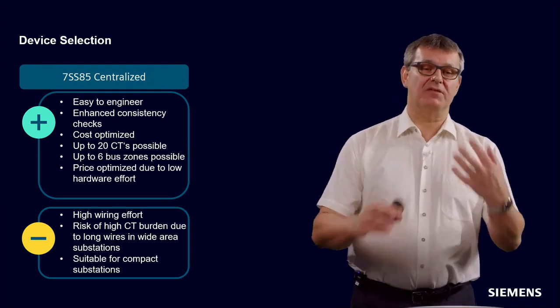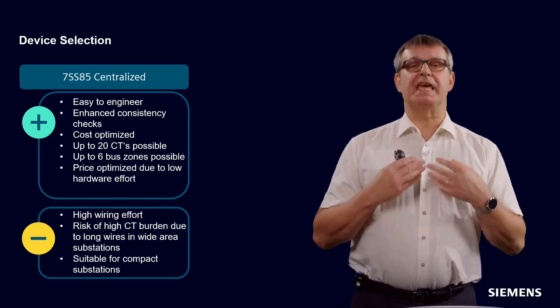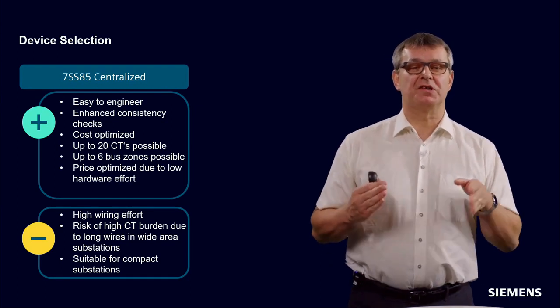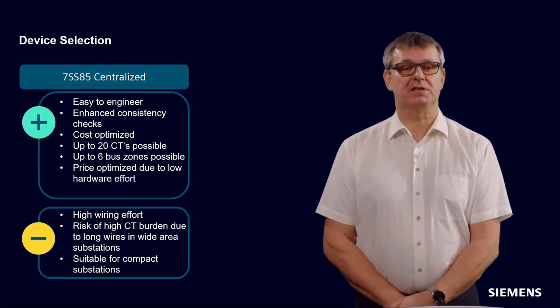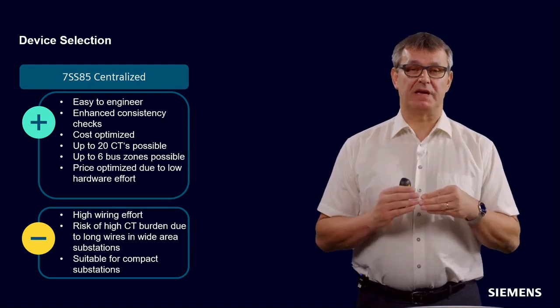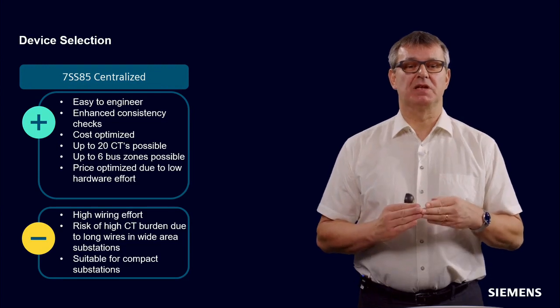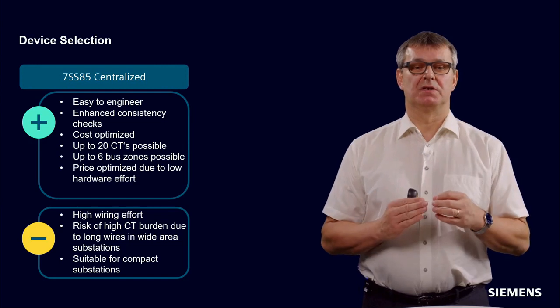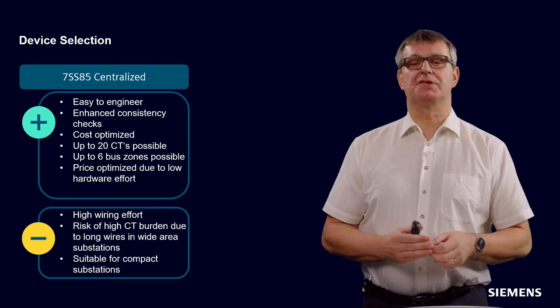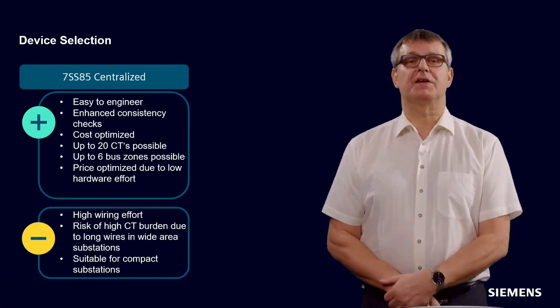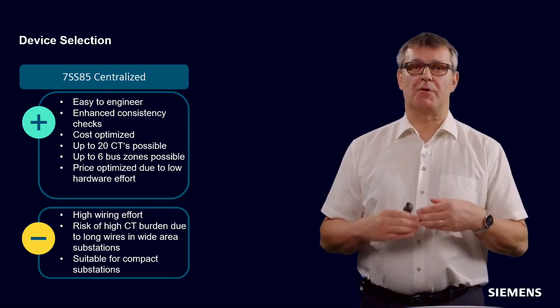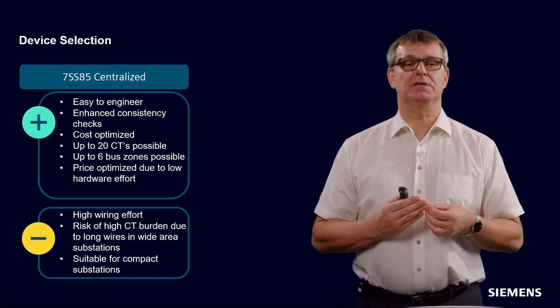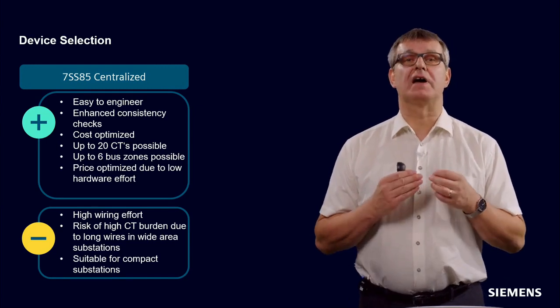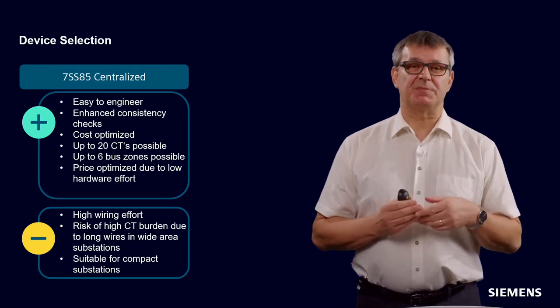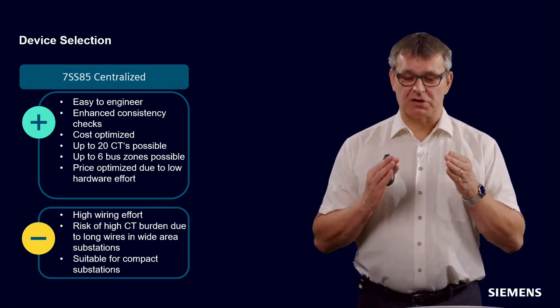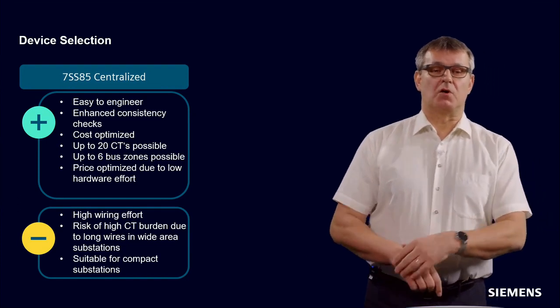It may be a high wiring effort because all the binary inputs, all the cables of the binary inputs, of the binary outputs, of the CTs must be concentrated at one device. So it's a quite high wiring effort. Here, very important, if we have a large air-isolated substation, we will have a risk of a high CT burden, because these long cables from this decentralized system from one bay, which may be 200 meters away from the center unit, you need a very long cable, a very long wire, and this leads to a high CT burden. And this high CT burden can lead into an earlier saturation of your CT. So the centralized busbar protection is mostly only suitable for GIS substations. Suitable for compact substations, as already said.